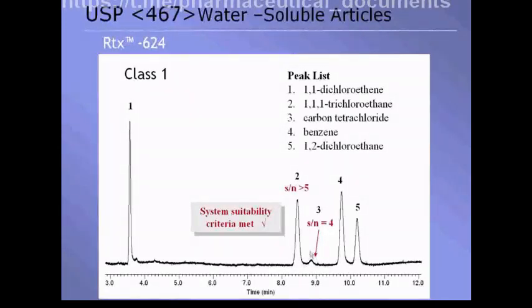But as we see here, under those conditions, we did meet the analytical specs needed for system suitability, or really proving that this system is suitable for use. These are the requirements listed inside the method. And we can also see on this low sensitivity why it was so important that we make sure that we get good solubility and minimize excessive disturbances in preparing the Class 1 standard. Any loss in analyte could be significant in actually failing system suitability.